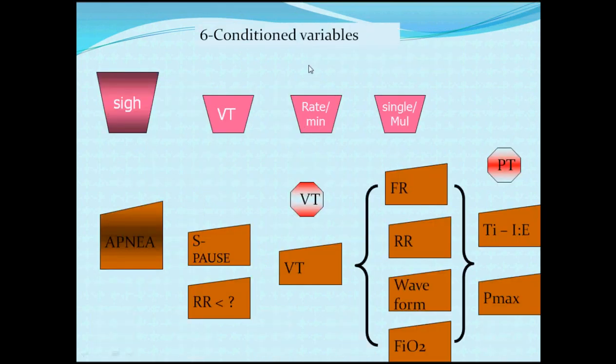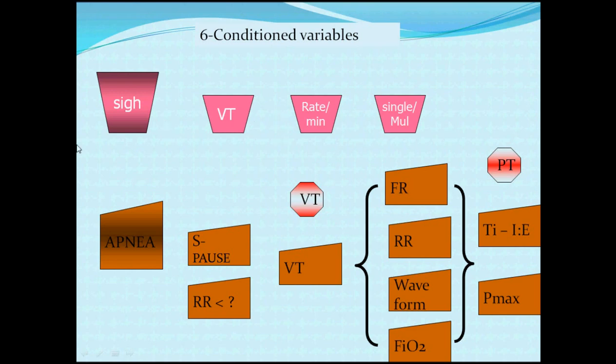The next component is conditional variables. A conditional variable means: if something happens, you do something. For example, delivering the same tidal volume repeatedly may lead to some dysfunction of the lung, so you need to mimic normal physiology by occasionally delivering a slightly higher tidal volume at a certain rate — either multiple or single times per minute. This is called a sigh breath (SI), and its function is to open the lung and increase oxygenation.